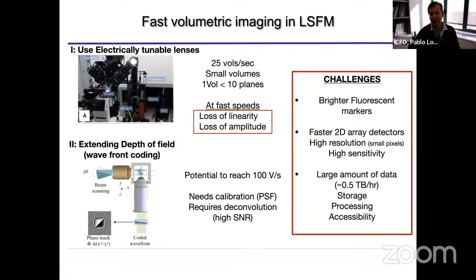First of all, we need to have brighter fluorescent markers. If we have brighter fluorescent markers, the signal-to-noise ratio will be higher. This is one condition that we need. Second condition, we are driving our CCD cameras or sCMOS cameras as fast as they can go. Obviously, the faster you go, the smaller the photon budget. So one way to solve this problem is to do binning or to have larger pixels. But if we do that, we lose resolution. So we want high sensitivity, but also very high resolution. The third challenge that is really important is that if we are capturing very fast volumes, lots of 2D planes, in a few minutes, we will have lots and lots of data that needs to be stored, processed, and accessed. So these are some of the challenges that we are facing just now in light sheet microscopy for trying to get fast volumetric imaging.